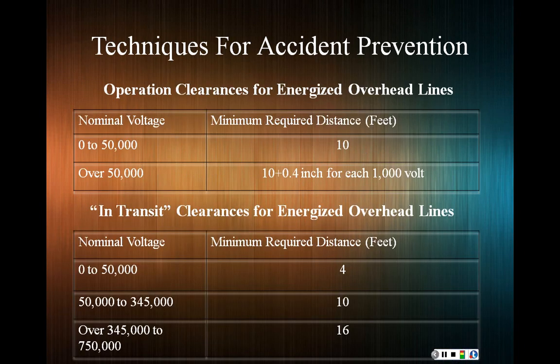Operation clearance for energized overhead lines, usually up to 50 kilovolts, is 10 feet. The minimum required distance is 10 feet based on OSHA, and if the voltage is more than that, it's 10 feet plus 0.4 inches for each 1000 volts. And in transit, if it is less than 50 kilovolts, there should be 4 feet, and if it is more than 345,000 volts, it should be 16 feet.